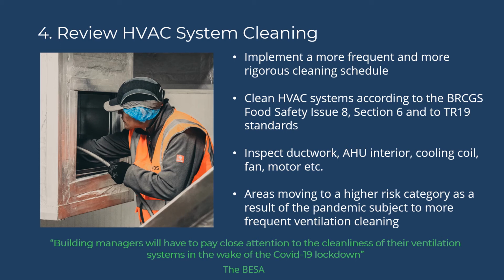Cleaning should also be carried out to TR19 and the new TR19 grease standards. TR19 establishes safe levels of ventilation hygiene for all types of building and mirrors the international standard BS EN 15780.